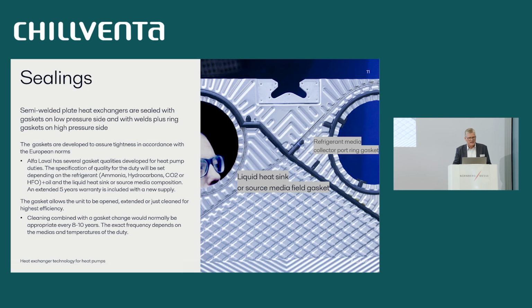And the gaskets allow the units to be opened and extended, so it's only an opportunity. Especially when you have a dirty source media, this is of course very good. An opening could be every 8 to 10 years to clean the unit, depending on the auxiliary equipment. I will come to that. An extended 5 year warranty is included with a new supply of these heat exchangers for heat pumps.